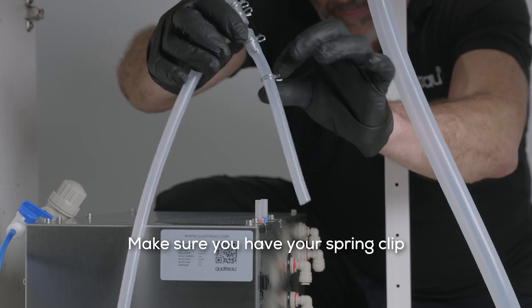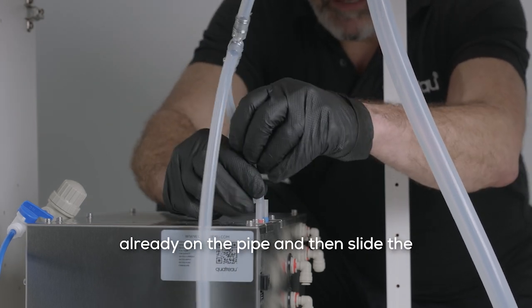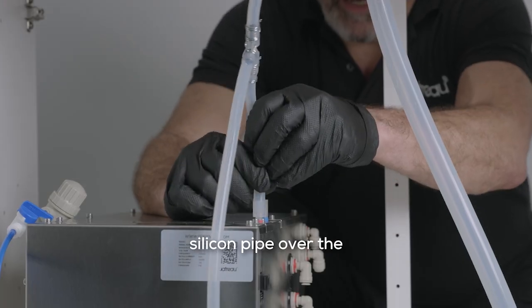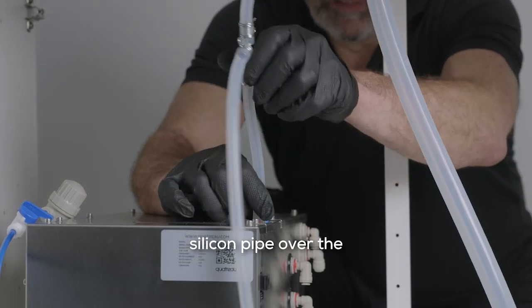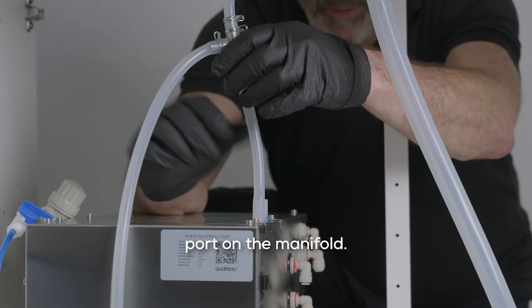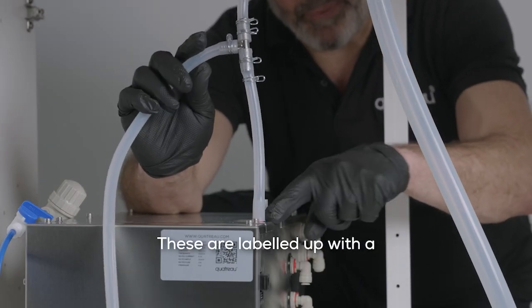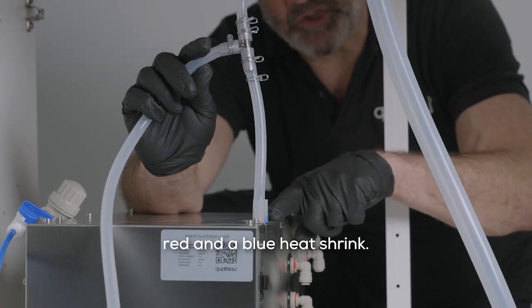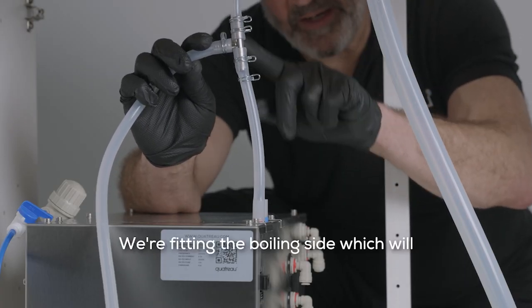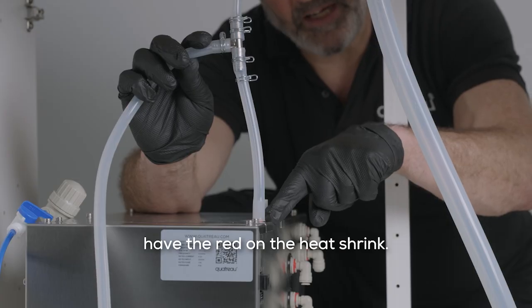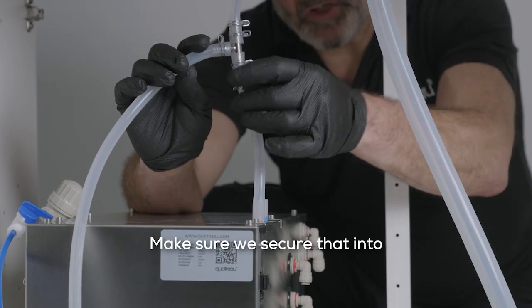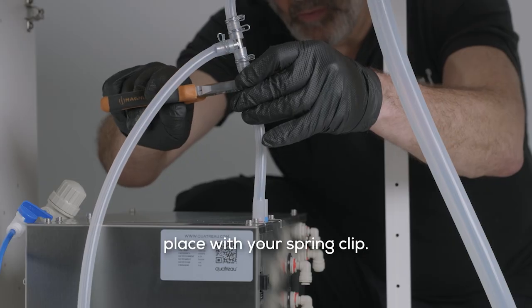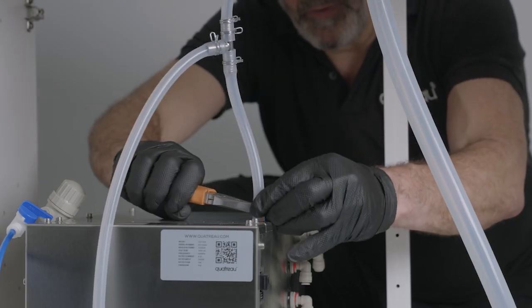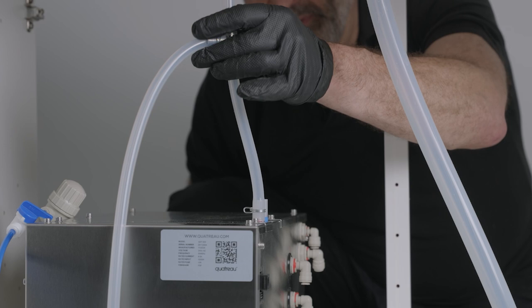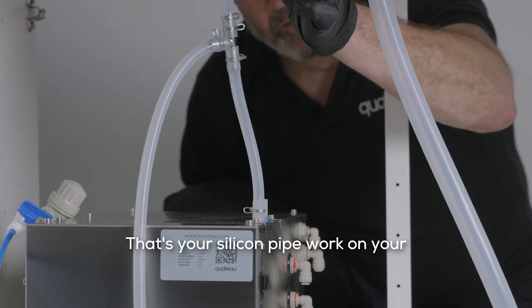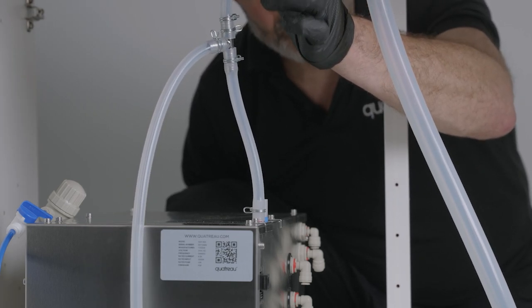Make sure you have your spring clip already on the pipe and then slide the silicone pipe over the port on the manifold. These are labelled up with a red and a blue heat shrink. So we're fitting the boiling side, which I have the red on the heat shrink. Make sure we secure that into place with your spring clip. That's your silicone pipework on your boiling side of your water heater control unit.